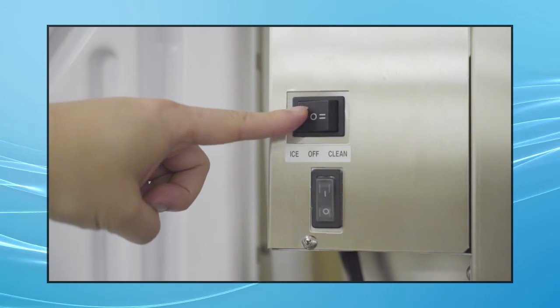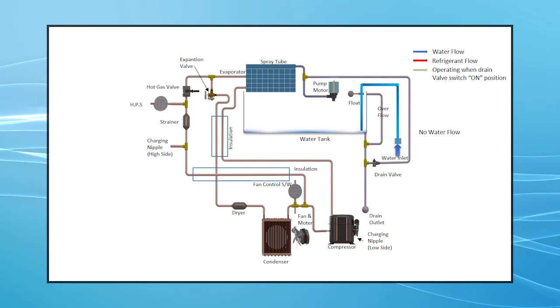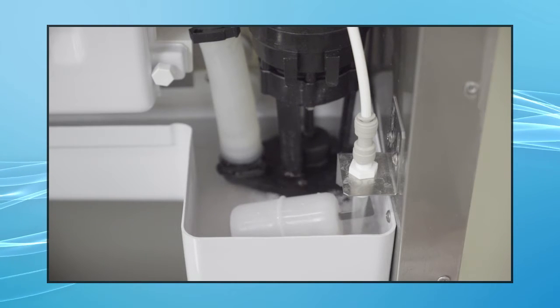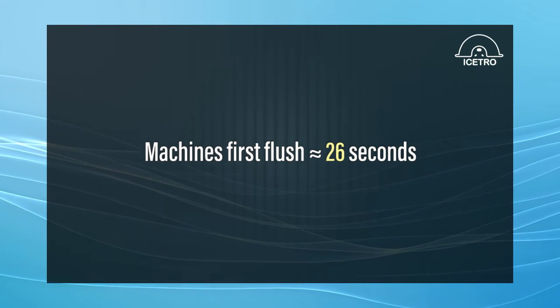The drain valve will open and water pump will turn on. The control board relay for each component is clearly marked and when it operates will have a light turn on next to the marked relay. The machine's first flush lasts about 26 seconds.